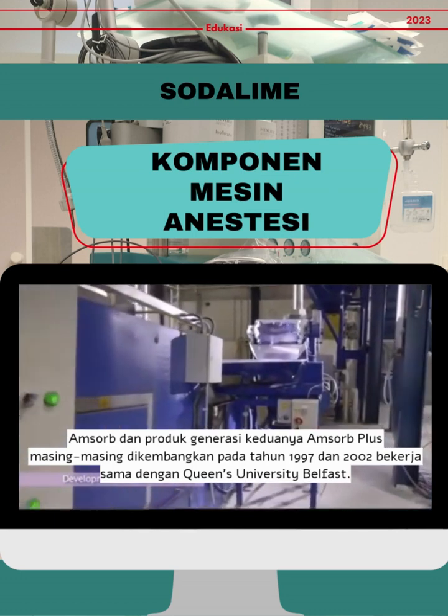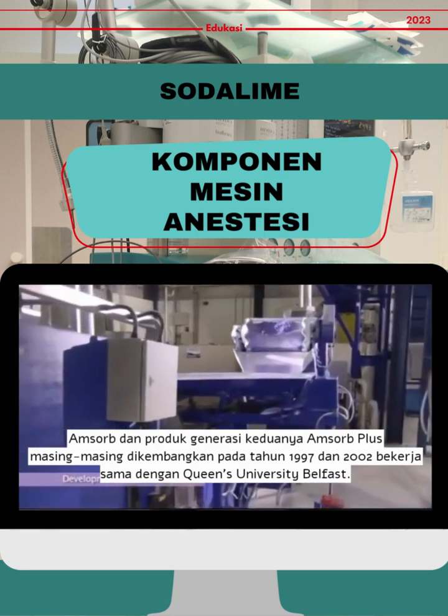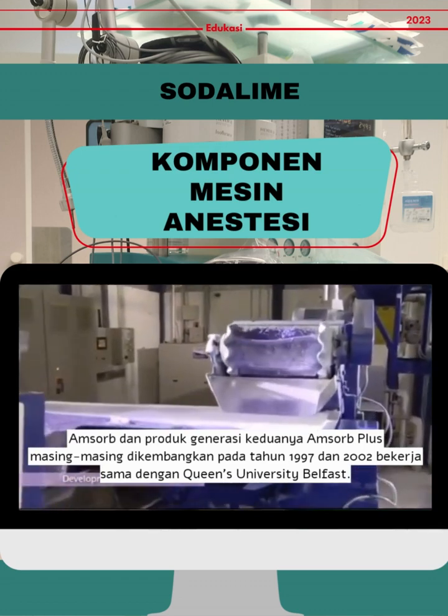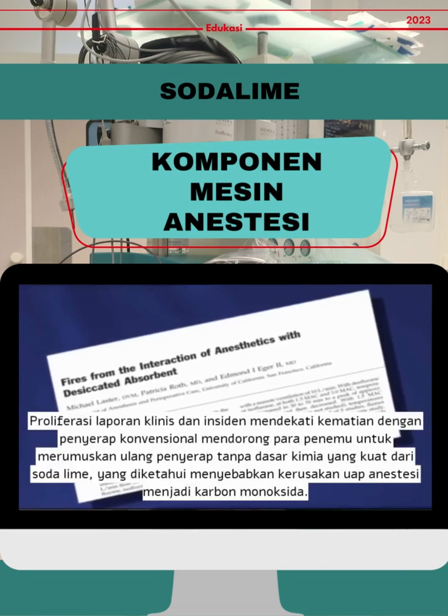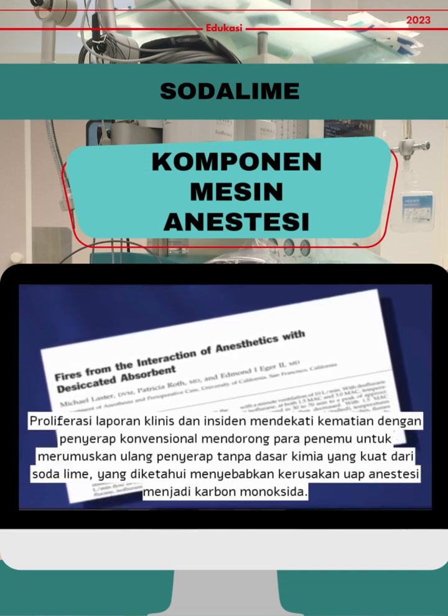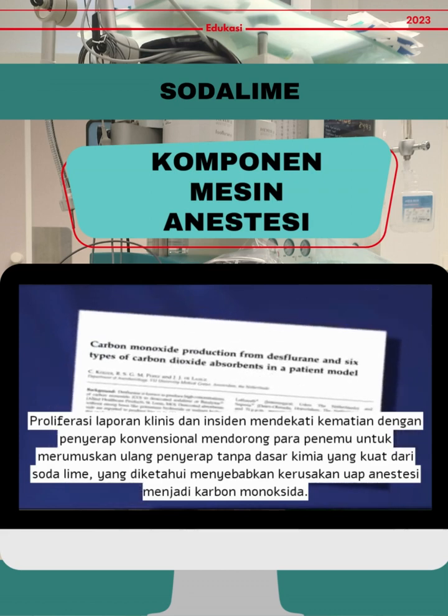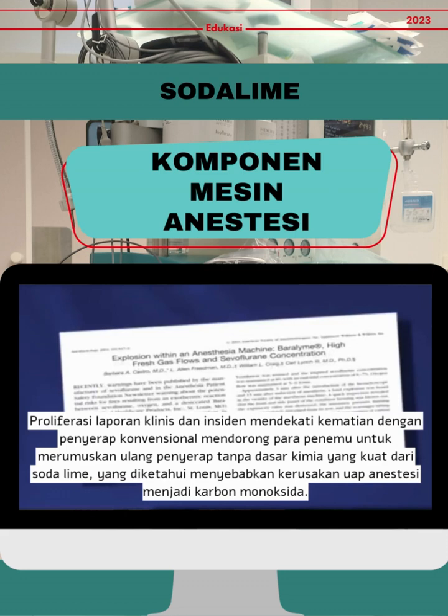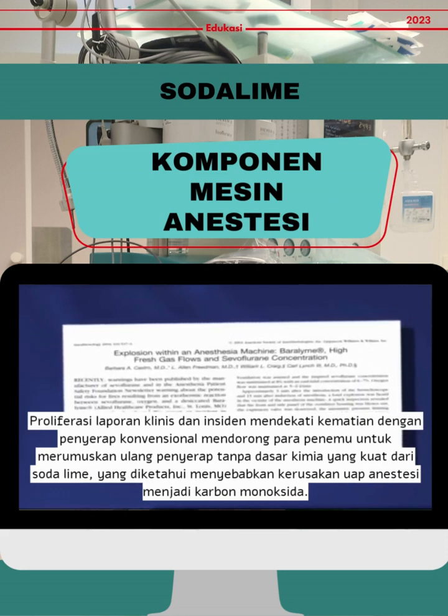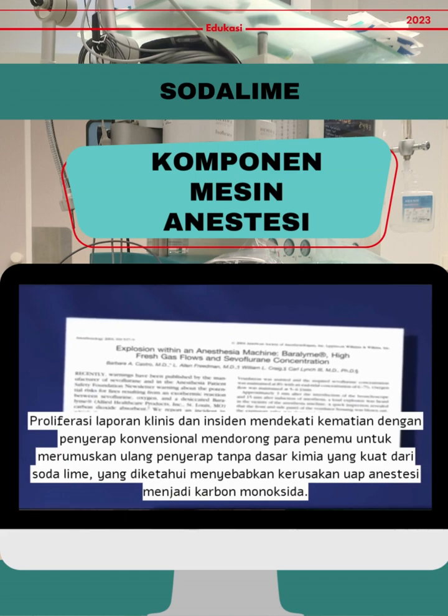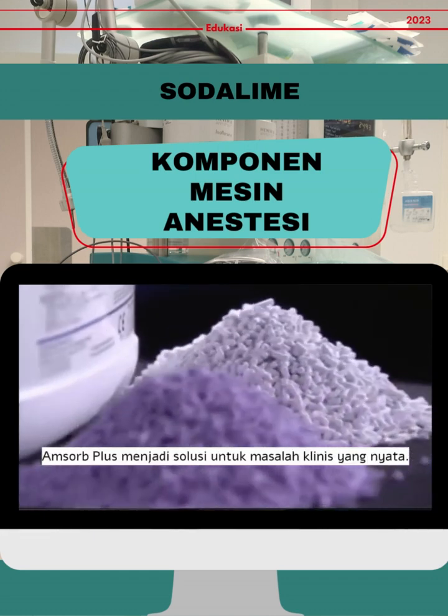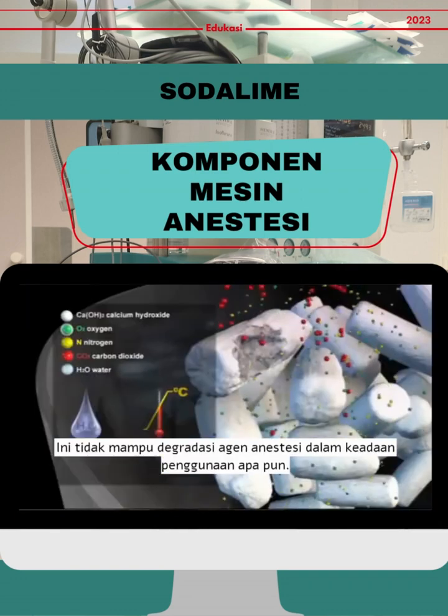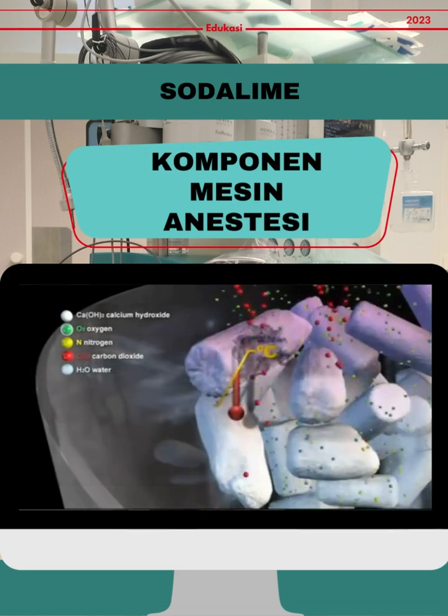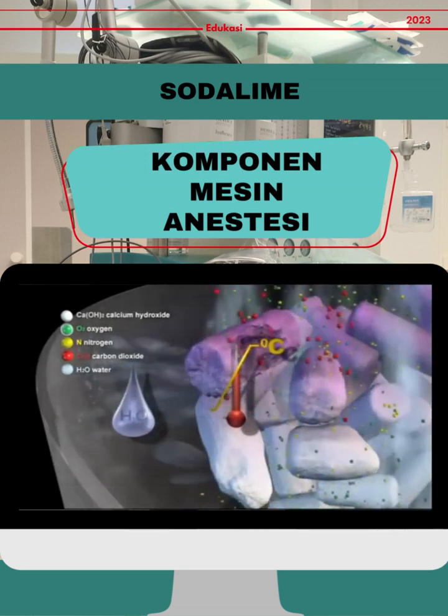Amsorb and its second-generation product, Amsorb Plus, were developed in 1997 and 2002 respectively, in collaboration with the Queen's University Belfast. A proliferation of clinical reports and near-death incidents with conventional absorbents prompted the inventors to reformulate an absorbent without the strong chemical base of sodalimes, which were known to cause destruction of the anesthetic vapor to carbon monoxide. Amsorb Plus became the solution to a real clinical problem. It's incapable of degradation of anesthetic agents in any state of use. It simply absorbs carbon dioxide.